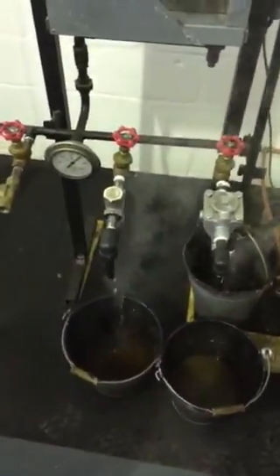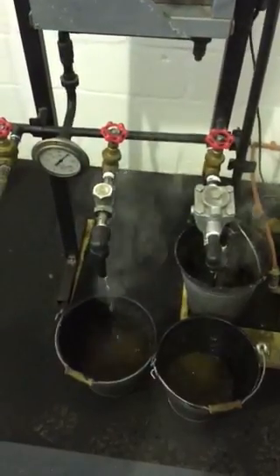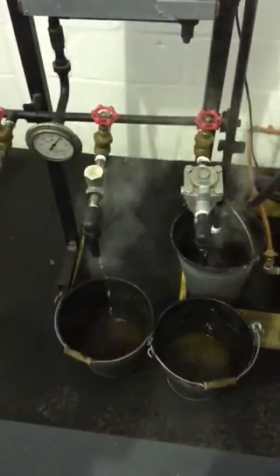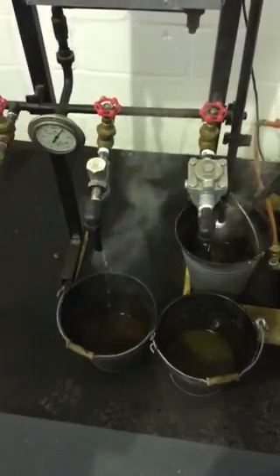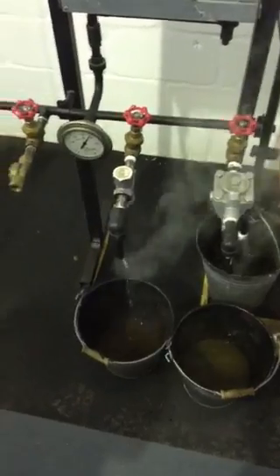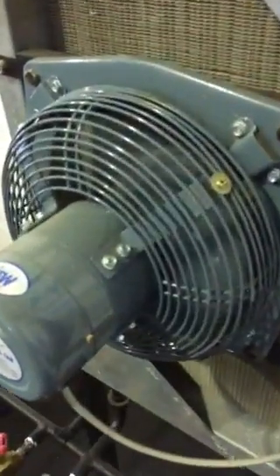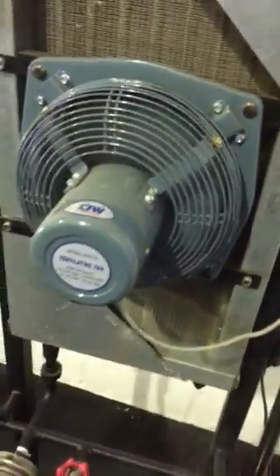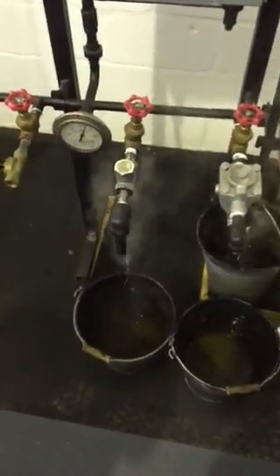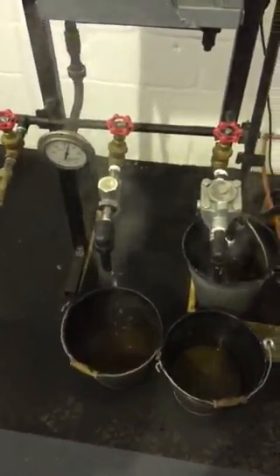It's going and discharging now, working under exactly the same load conditions. You can see that when we turn the fan on the unit off, the Venturi orifice steam trap continues to just handle the change in load and discharge efficiently.